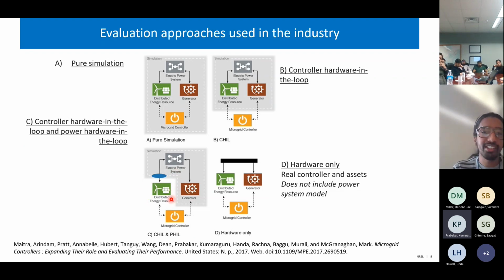The key difference between this and pure CHIL is that sometimes you're not able to model the inverters or some power hardware very accurately in EMT, so this becomes a major advantage. Maybe the inverter manufacturer doesn't want to share their model, so we can work with utilities, bring the same inverter and same firmware, and run those for hardware in the loop.